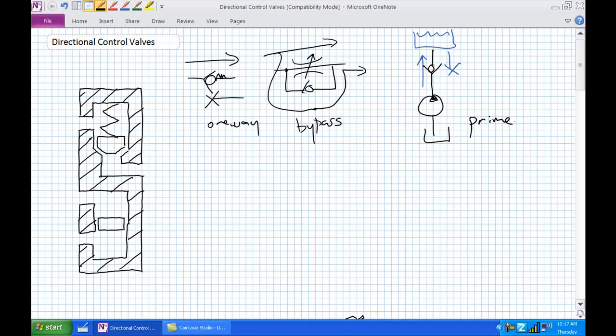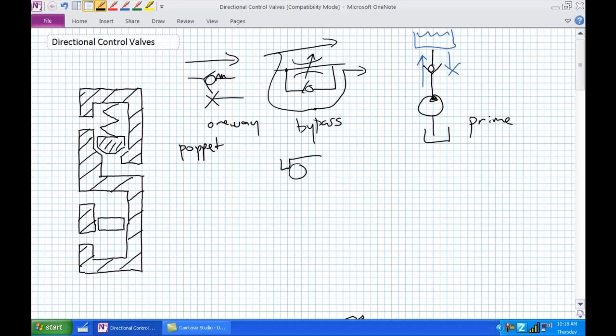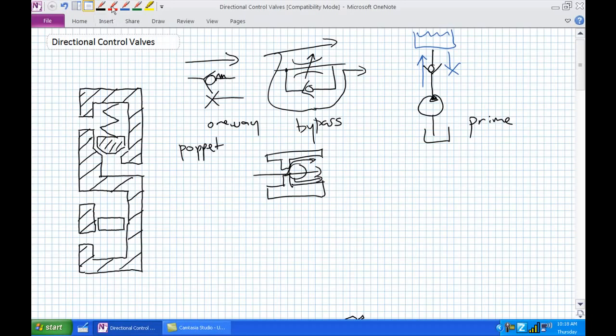Those are applications for a typical check valve, but I want to go into a little more detail. I've got a cutaway here showing not a ball but a poppet — a bullet-shaped object that fits in the passageway. This is a right angle check valve. In a direct-acting valve, fluid pressure pushes the ball out of the way but it's still in the passageway. In a right angle check valve, fluid pressure pushes the poppet out of the way so it doesn't interfere with fluid flow.